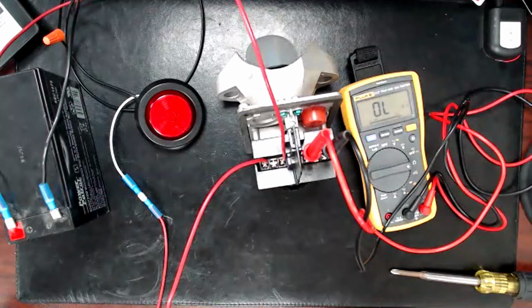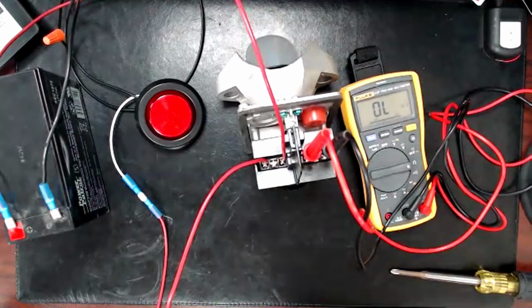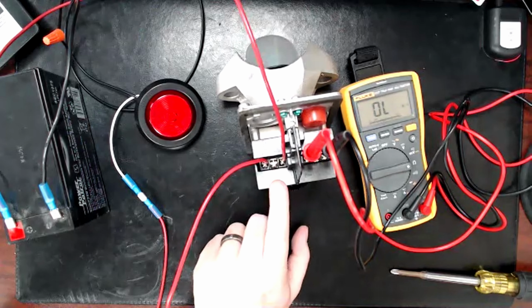If you've seen it where we've used just a dedicated NAC circuit and it goes straight from the power supply, chances are that was probably a Silent Knight or Fahrenheit system. Those have intelligent, programmable, individual NAC circuits, so we can actually dedicate one of them as the water flow bell circuit, and we can do all this in programming instead of using this switch here.